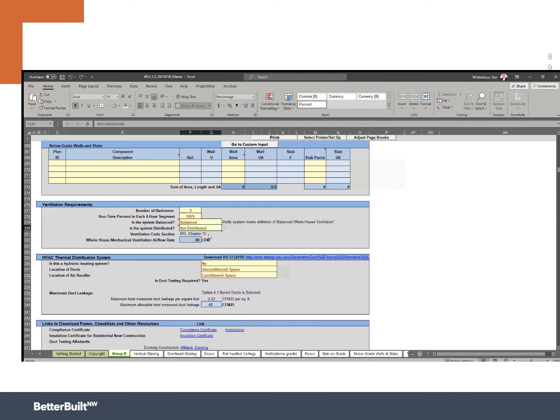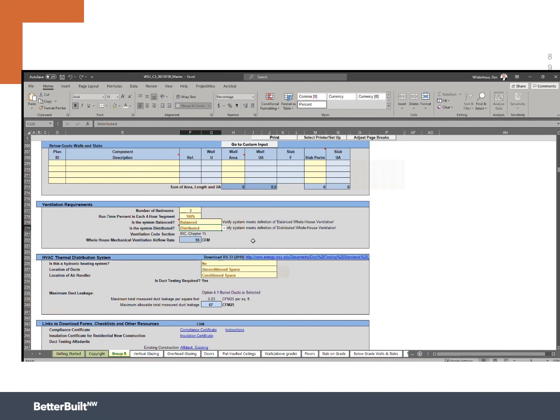So this could be that scenario where I've got a pipe coming into the return side of my central air handler for my furnace or my heat pump. And I've got an exhaust fan paired to run at the same time. We call those interlocked, meaning that control keeps them both running at the same time. Look at this, we only now need 55 cubic feet per minute if we're running it continuously.